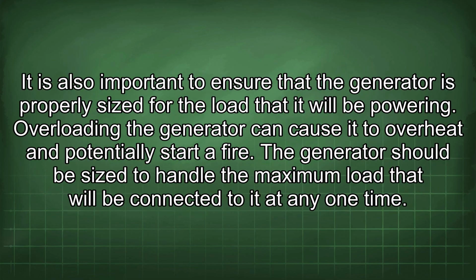It is also important to ensure that the generator is properly sized for the load that it will be powering. Overloading the generator can cause it to overheat and potentially start a fire. The generator should be sized to handle the maximum load that will be connected to it at any one time.